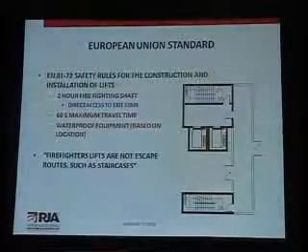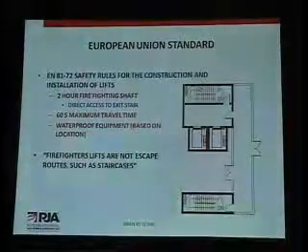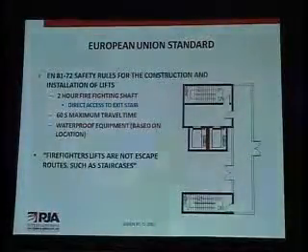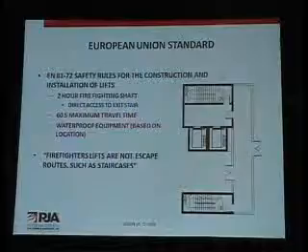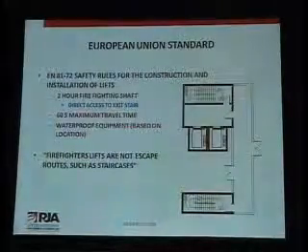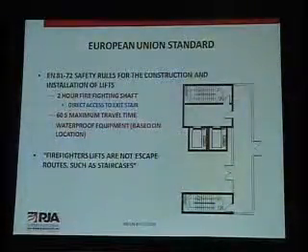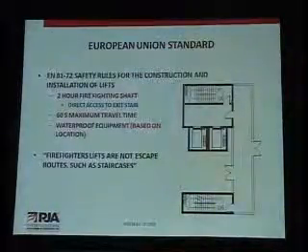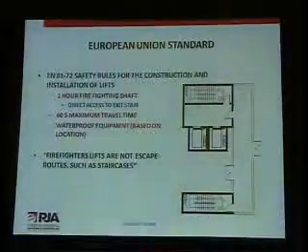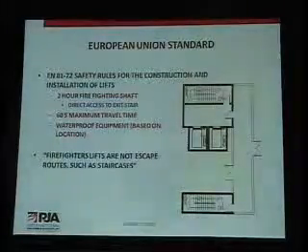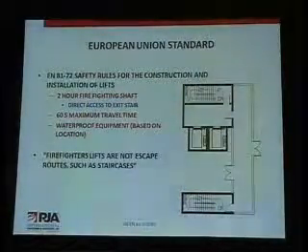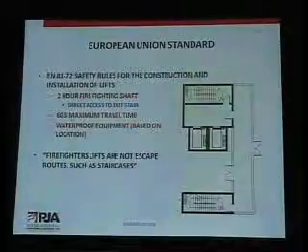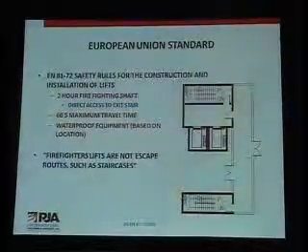As Jim had mentioned, some limitations include a 60-second maximum travel time to reach all floors, which in Burj Khalifa is not possible, especially when you consider that a single rise elevator is not possible in the building. You need to have transfer floors, and that's consistent with many super tall buildings. I can't think of any that I've worked on that haven't had a transfer floor, and really you'd be limited to, and these guys could probably correct me if I'm wrong, 100 stories at the very maximum, maybe a little bit more, maybe a couple more floors after that, depending on the height of the building.